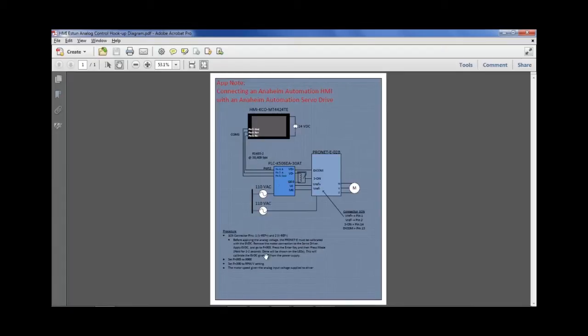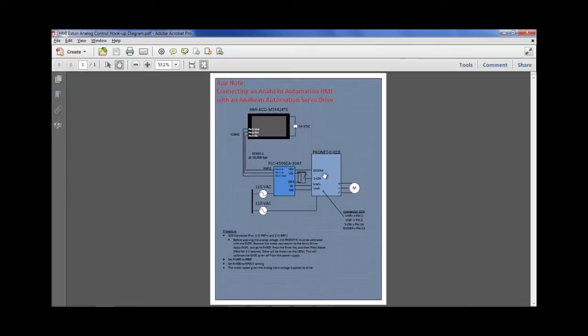In order to operate the servo motor in analog mode, we must set the speed reference offset in FN003, set the control register PN005 to 0 as well as the speed reference input gain register PN300. Currently it is set to 300 RPM per volt. Once all these are done, we can begin varying the input voltage on VREF plus and see the motor run at various speeds.